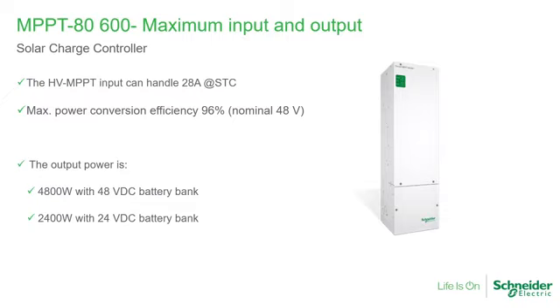The input, which is on the PV side, is 28 amps, which is fine because you will typically have 1 or 2 strings, so you'll unlikely exceed that. It has a high efficiency of power conversion, which is at 96% for a nominal 48 volt system. I mentioned before that it can work on a 24 volt or a 48 volt. The array changes a little bit, right? Because when the voltage decreases, so going from 48 to 24, the array size is going to change. So for a 48 volt nominal system, that means the batteries are 48 volt nominal, the array is about 5,000 watts, so 4,800. However, oversizing is perfectly acceptable.